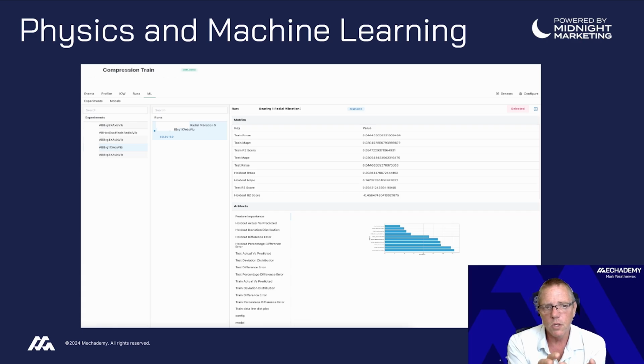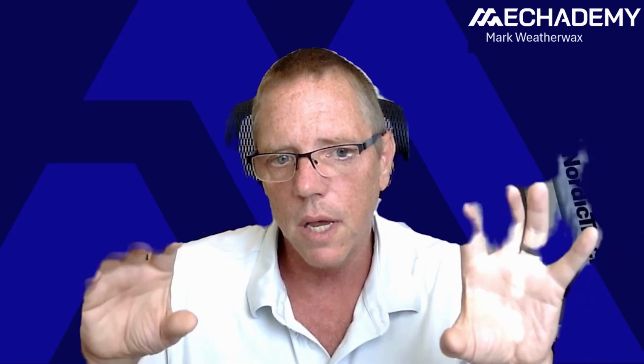And then the next thing that we do here is there are certain areas where we are real strong believers in machine learning. Machine learning, in our perspective in the machinery space, has been extremely powerful at figuring out the underlying physics on complicated things, and one that we use it a lot on is vibration. You can go through, make sure that from a physics standpoint, you're running in normal operating conditions. You can then train a model on that data for the vibration conditions, or combustor, or exhaust cylinder temperatures. There's a lot of those complicated things that you can then train it on. And now you have something that's running that's giving you a deviation. When we get to how we manage diagnostics and alerts, you'll see we pull these together based on what root cause we're actually trying to diagnose, as you come down and put all these different modes together. So physics and machine learning are tied. They go together. One could go before the other.